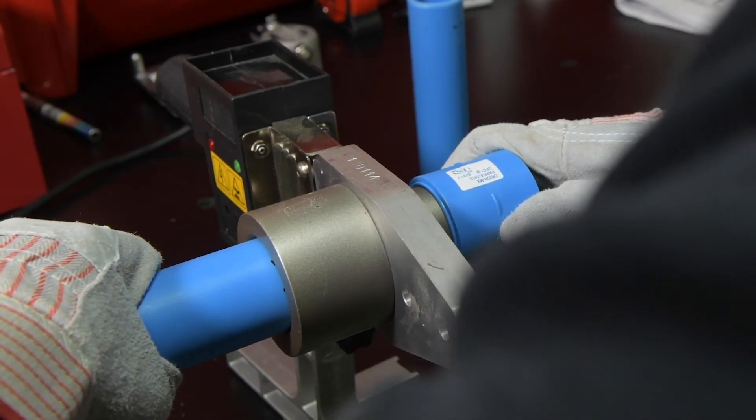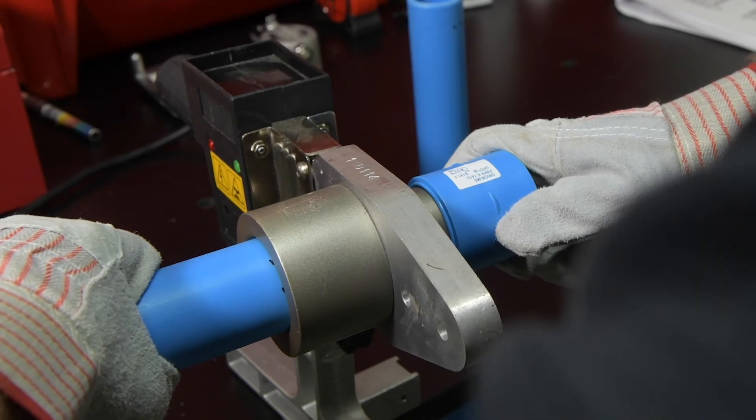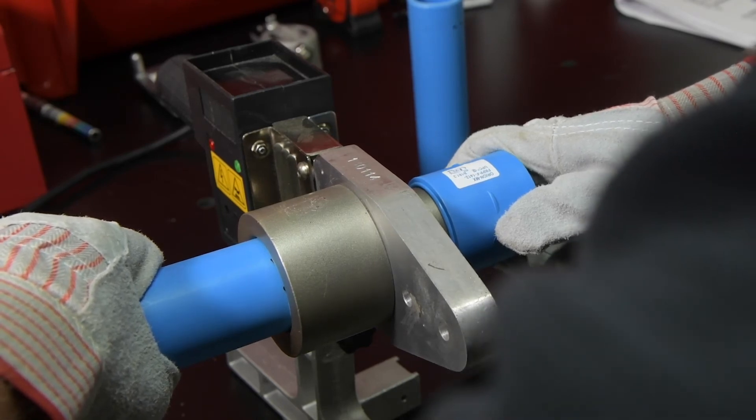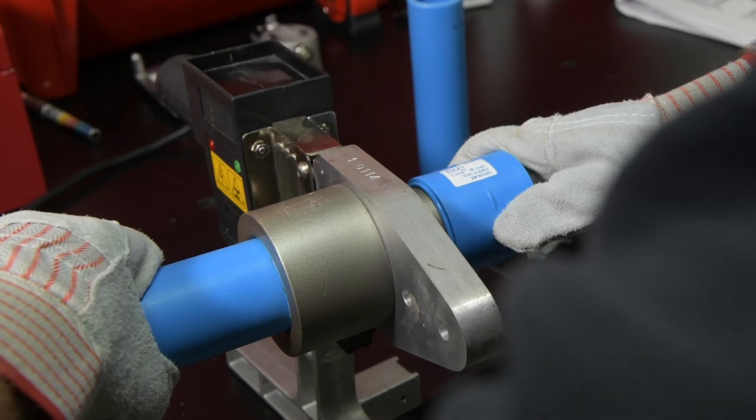Keep both pipe and fitting perfectly straight on the tool as they're heating. Letting them sag downwards or pulling them towards you will deform the connecting surfaces, which can result in a poor fusion.